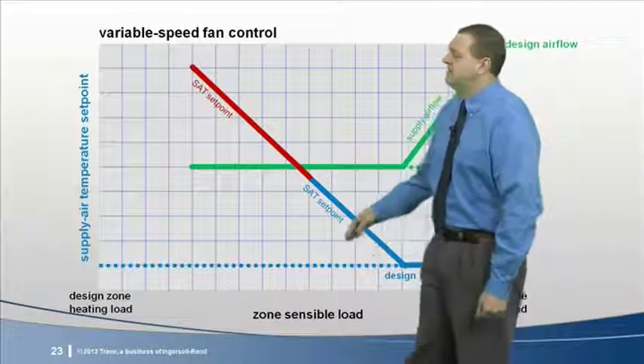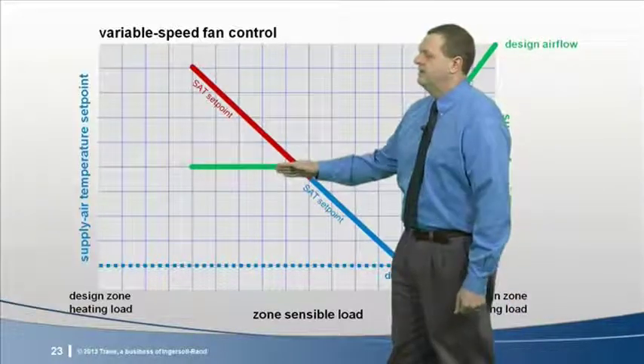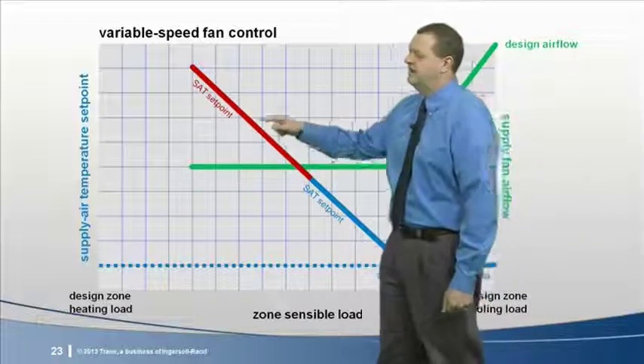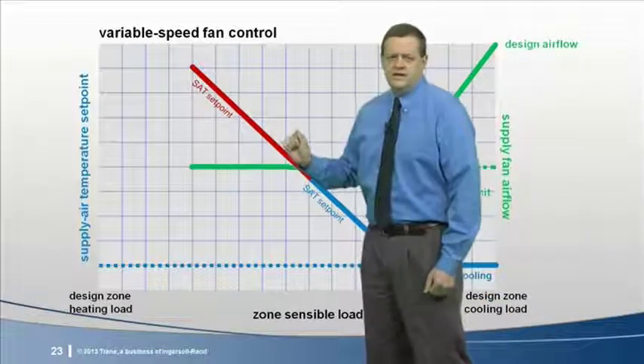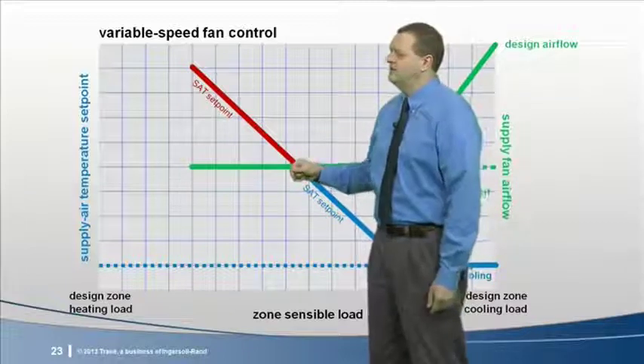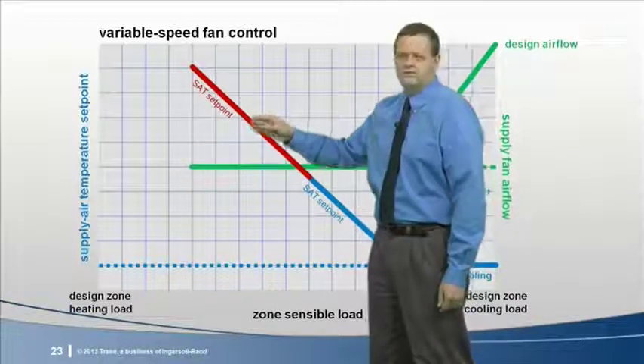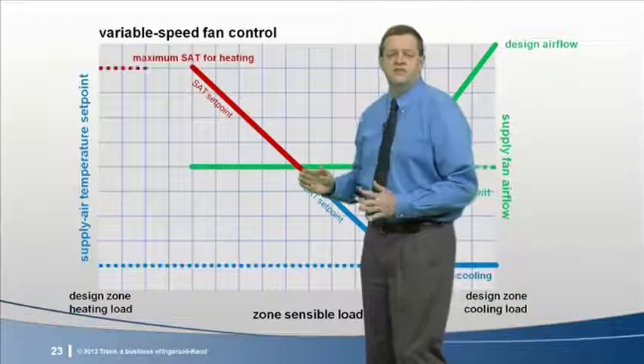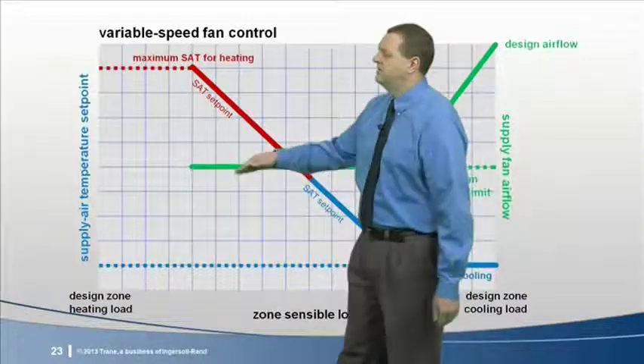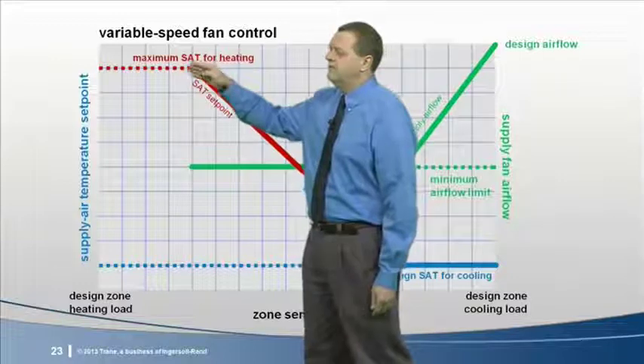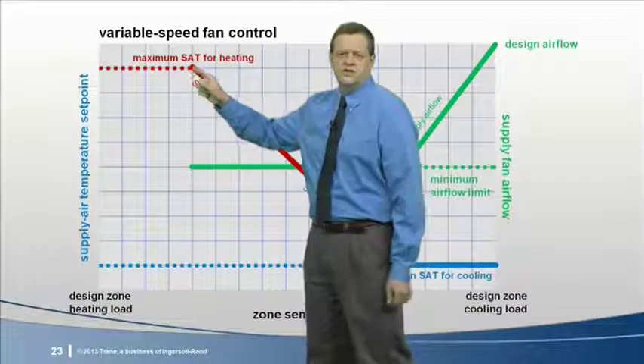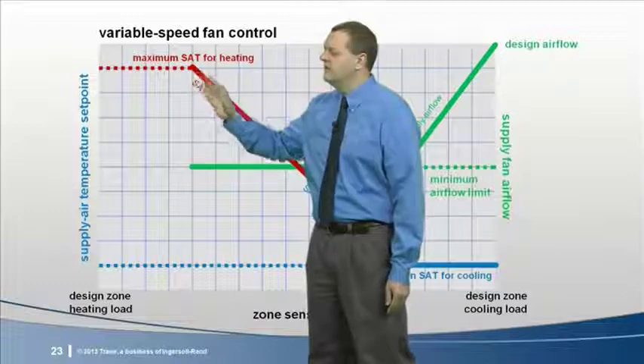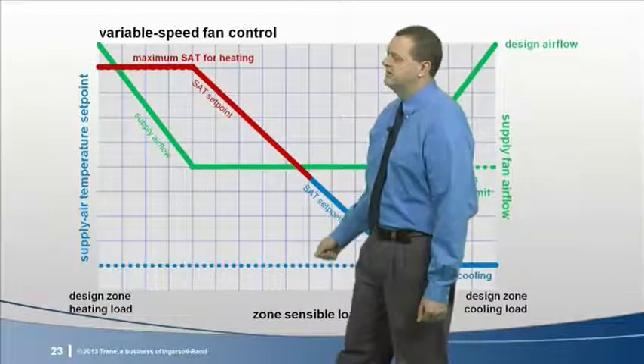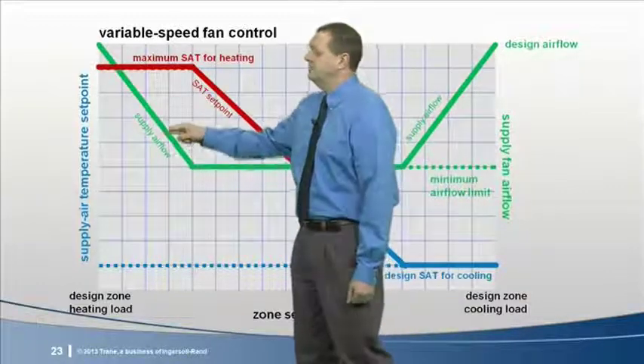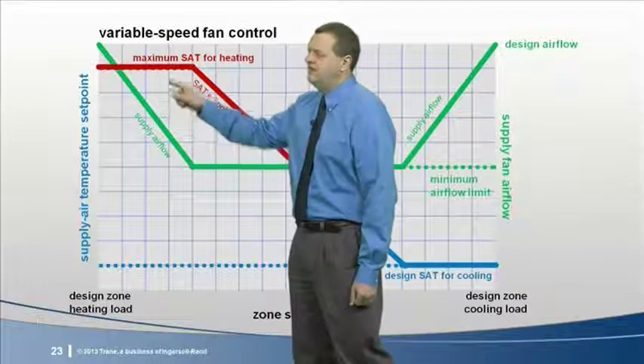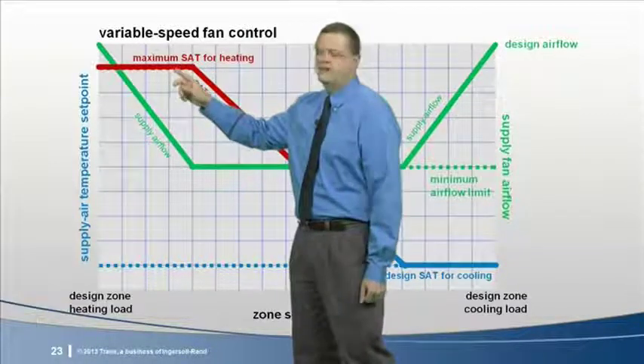The fan continues to operate at minimum airflow, and the supply temperature set point is reset upward even further. Heating capacity is staged or modulated to maintain this new supply temperature set point. Eventually the zone heating load may increase to the point where the supply temperature reaches some preset maximum limit. I'll circle back to discuss this limit too. As the zone heating load continues to increase, supply airflow is again increased, while heating capacity is staged or modulated to maintain the supply temperature at this maximum limit.